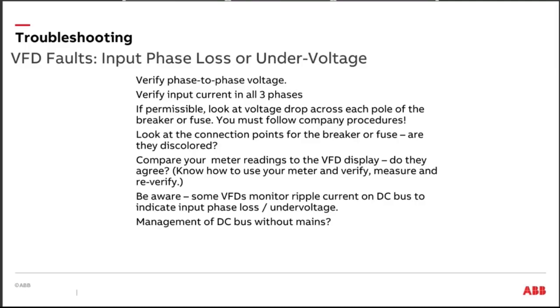If we have an outage take place and we have the drive set up, and it's easy to do, we could actually let the loading on the fan keep the motor shaft moving. If the motor is moving, as long as I can keep that shaft moving slightly faster than the rotating field, then the motor is a generator. And I can use that kinetic energy in that fan to keep the drive energized through the motor and waiting for the mains to come back up.